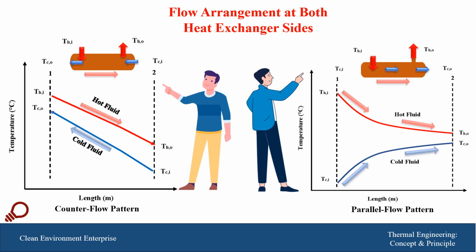And in general, all heat exchangers are preferred to have a counterflow. In the counterflow, there is a uniform temperature distribution and they provide a good temperature difference between both fluids. So it is more efficient than the parallel flow pattern.